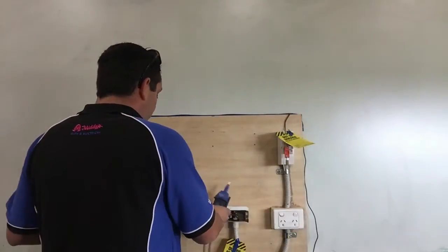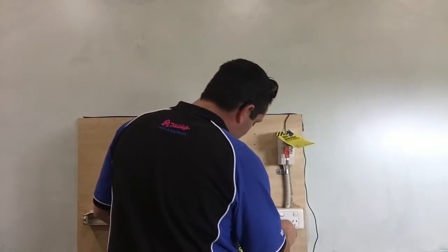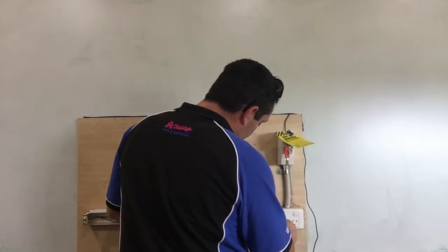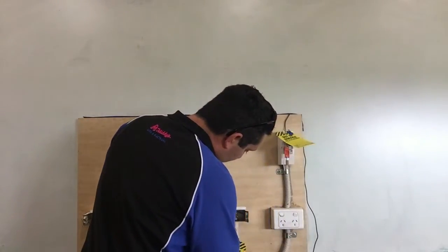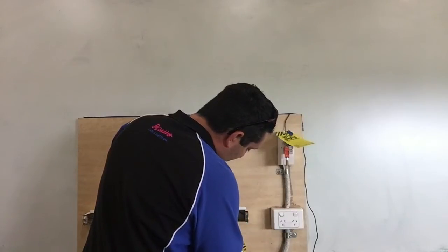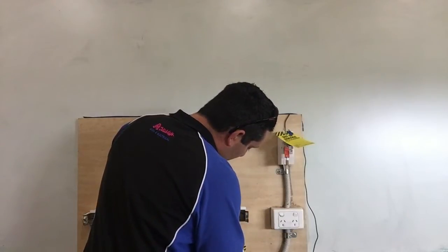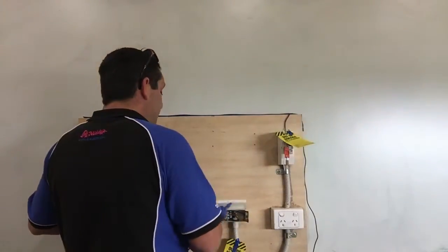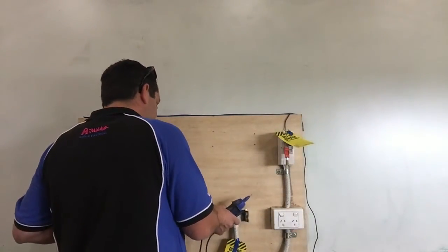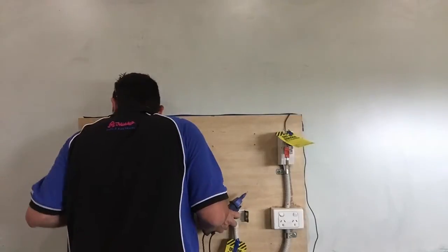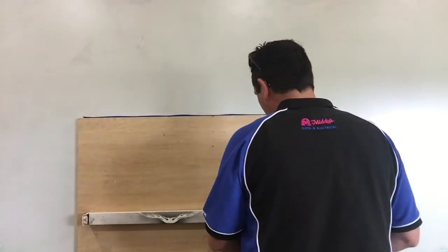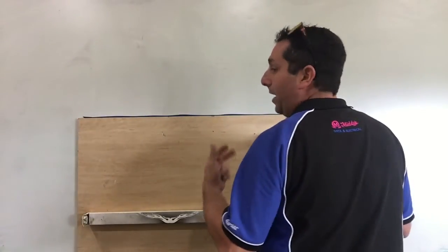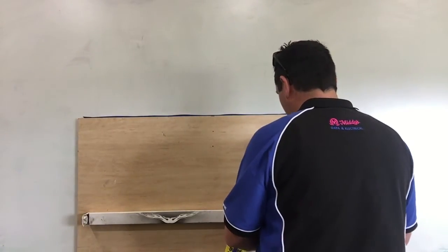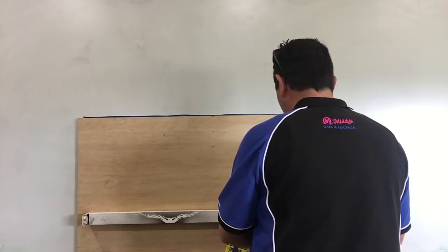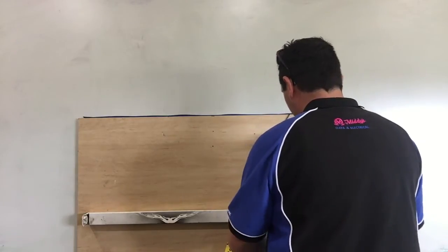We're going to remove our cover. We're going to test from our earthing point: active, earth, neutral. And we're going to test active, neutral, active, earth, neutral, earth. That shows that there is still power connected. Again, I'm going to put my cover back on. This step isn't necessary, but I'm going to test my tester again, because I'm going to get into the habit of every time I test, I'm going to retest my tester. Active, neutral, earth, neutral, earth.